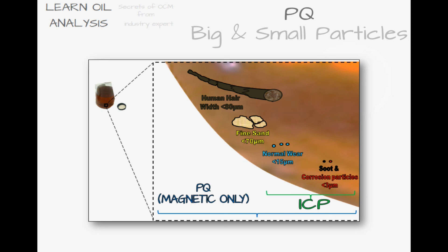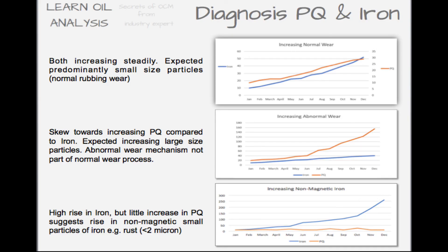This is important diagnostically because you can determine if the wear being generated is normal wear, usually less than 15 microns, or large abnormal wear particles. If ICP iron and PQ are rising together in a trend of historical samples without an oil change, this suggests the increase is in small particles. But if the PQ increases faster than the iron, this means that the abnormal wear process is occurring. If in contrast the iron is rising but the PQ is not, this suggests there is an increase in small non-magnetic particles such as rust. Consequently, the combination of PQ and iron is a good prognostic tool in condition monitoring.